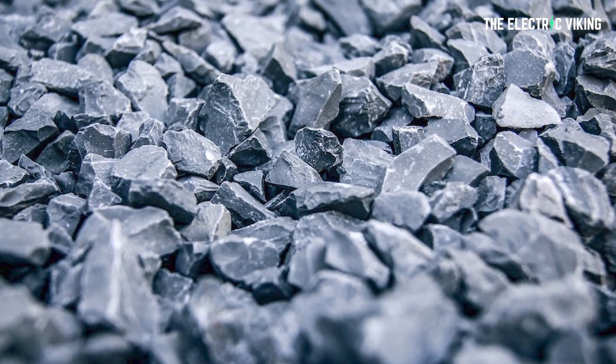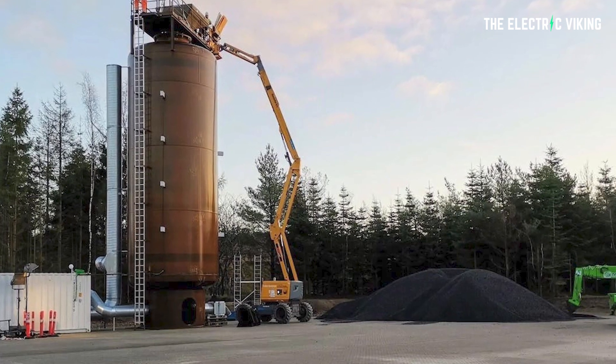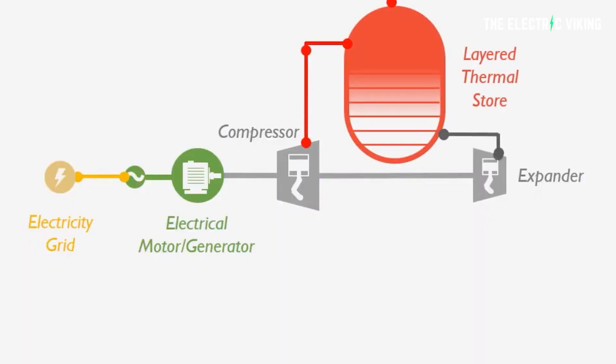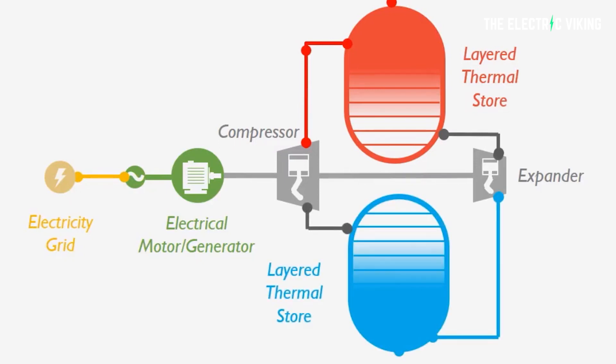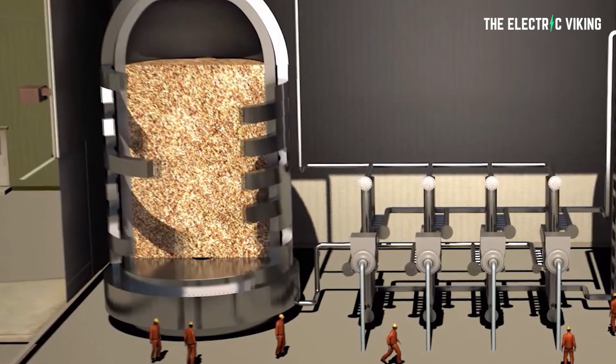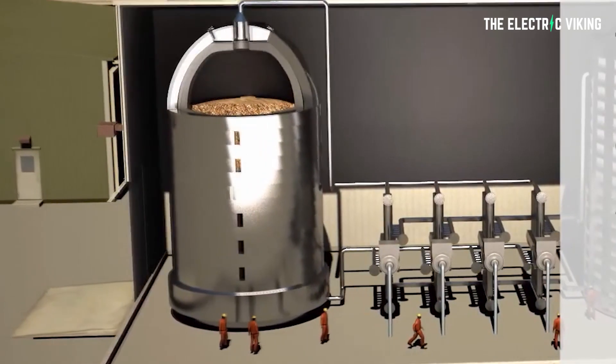The energy storage that Andel and Stiesdal are working on contains crushed stones the size of peas — very small stones — stored in insulated steel tanks. When there is an excess supply of electricity in the grid, the storage is charged using a specifically designed heat pump system, which moves heat energy from one set of tanks to the other. The stones get colder in the tanks from which energy is taken, while they get as hot as 600 degrees Celsius in the tanks that receive the heat, and they stay hot for quite a long time.